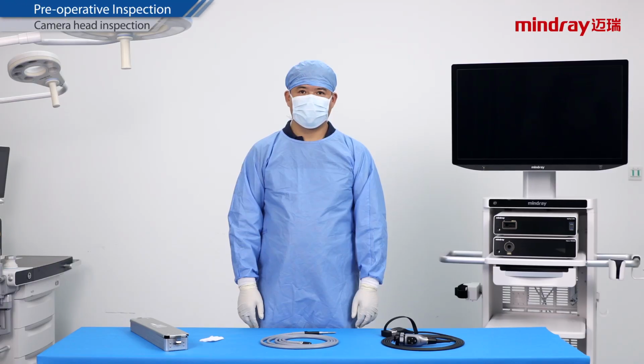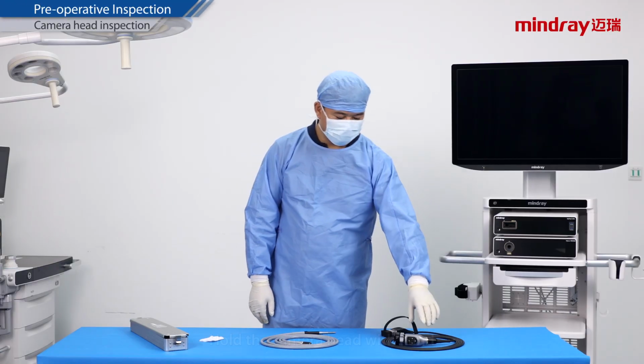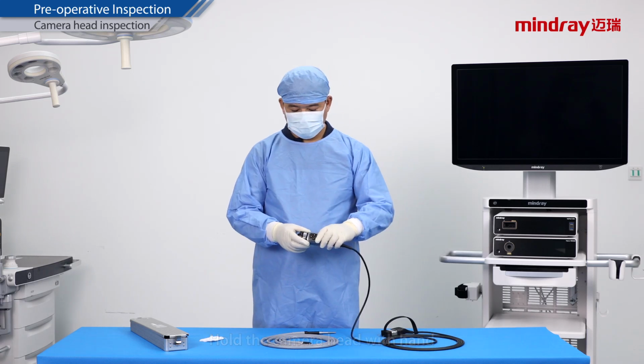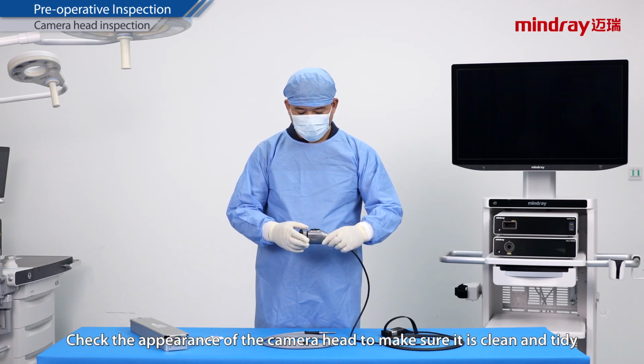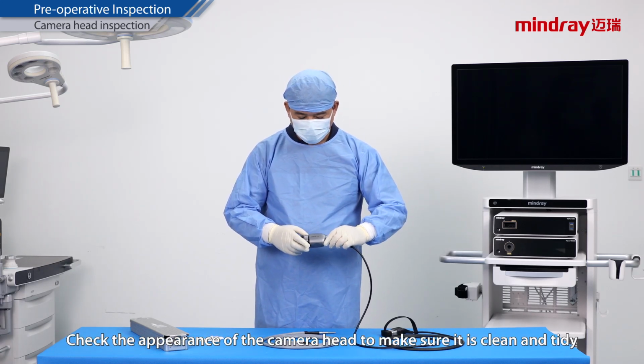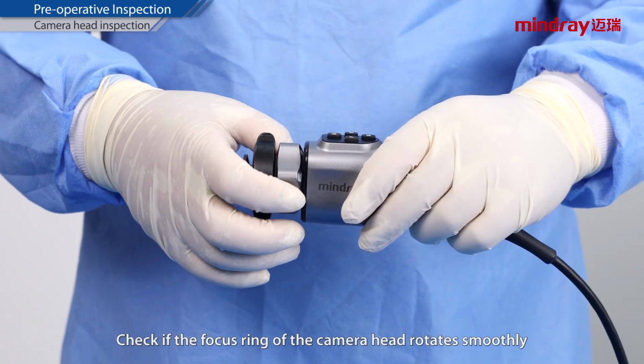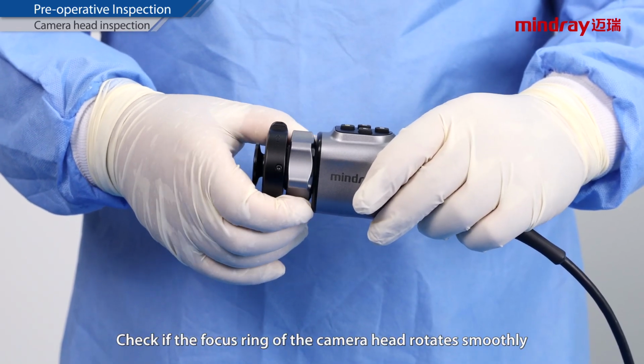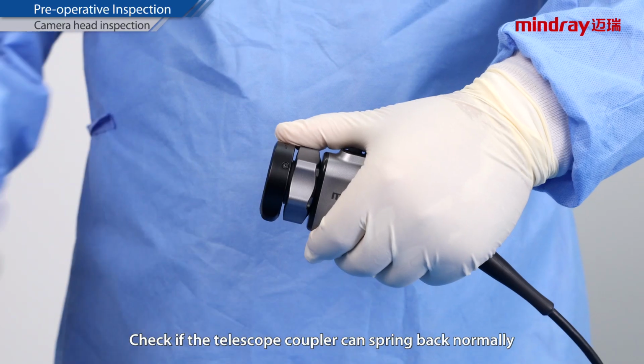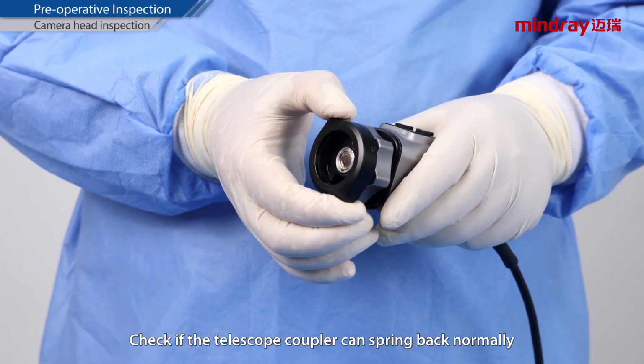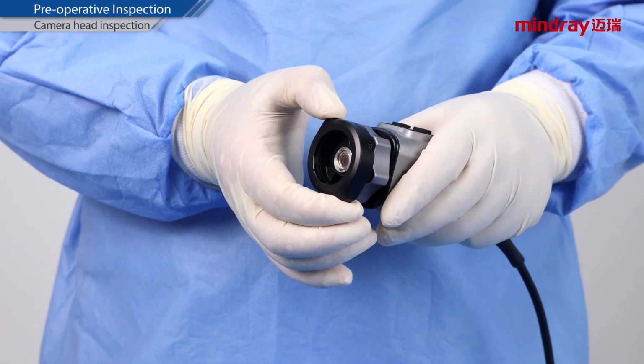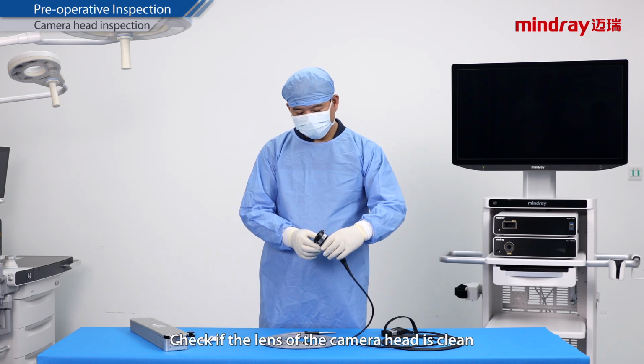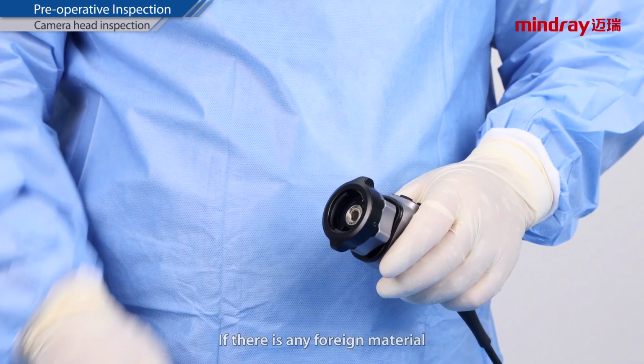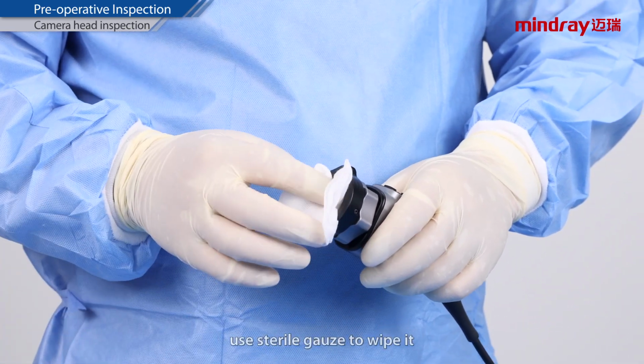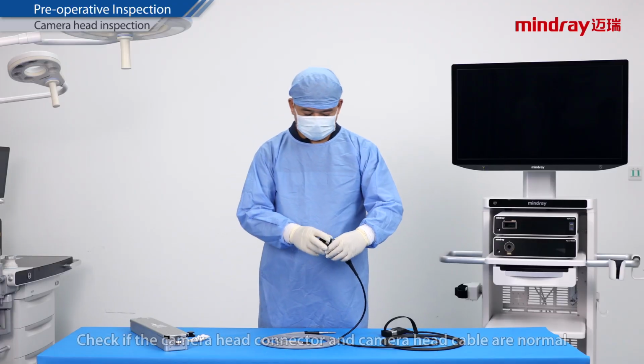Pre-operative inspection. Camera head inspection. Hold the camera head with hand. Check the appearance of the camera head to make sure it is clean and tidy. Check if the focus ring of the camera head rotates smoothly. Check if the telescope coupler can spring back normally. Check if the lens of the camera head is clean. If there is any foreign material, use sterile gauze to wipe it.